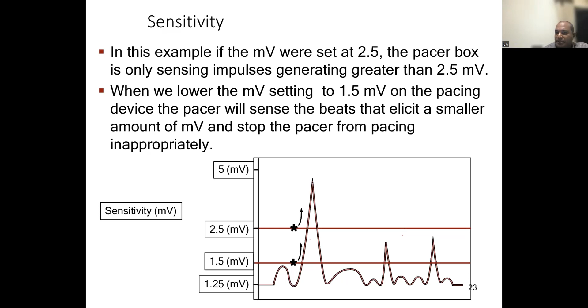And this can actually change from patient to patient. Again, it can change depending on the environment and other factors. But as a matter of fact, the standard pacemakers generally do well if you keep the sensing levels generally around 2 millivolts in the ventricle. In the atrium, it will be different, but it doesn't matter for you. In the ventricle, it should be around 2 millivolts or above. Generally, the ventricle activation will cause a current which goes beyond that level. So the pacemaker can generally see an effective cardiac cycle at that level.